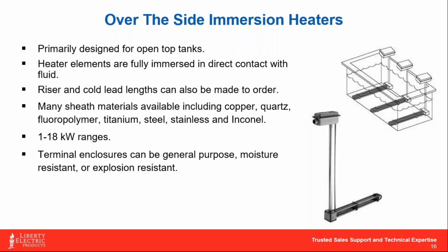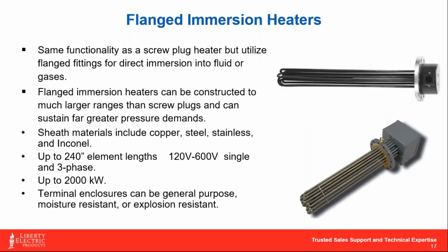These also have a wider range of element materials because of what they're subjected to. We can get into fluoropolymers and titaniums and quartz. There are some pretty exotic materials that can be used for these, but almost all of it has to do with corrosion resistance. Again, same thing as far as the kW ranges go, and whether or not you'd want the termination to be general purpose, moisture resistant, or explosion resistant.